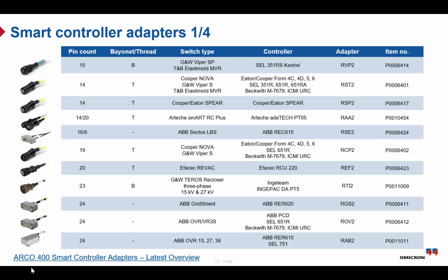For example, if the recloser is mounted high on the pole, you can connect the adapter at the top and perform testing from the ground. This makes the process much safer and more efficient. There are many types of adapters available to support different manufacturers and models. And if a specific adapter is not available, you can use a breakout box solution which allows flexible and custom connections for any setup.